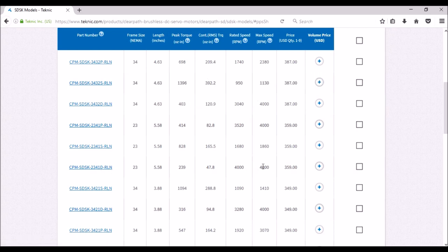You can see this by the max speed RPM. The S model is designed more for torque and less speed. You can see this again with the RPM rated at 1860 on this particular model, and the torque is 165. Whereas on the D, for the same model designation, your torque is 47, but your speed is 4000.